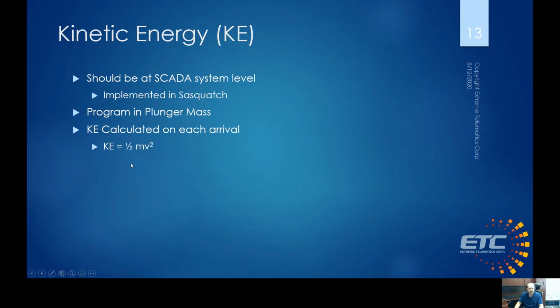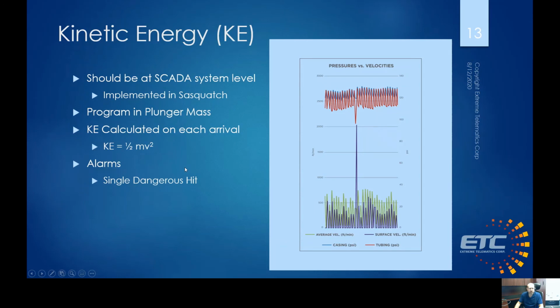And so we can calculate kinetic energy in imperial or metric. It's up to you. Those units can also be set in the sensor so that you get back the calculated value and the units that you want. And then once we have the kinetic energy, whether this is done in your SCADA system or whether it's done in the sensor itself, we can start to alarm in real time, because now we have every arrival's kinetic energy. Instead of just looking at the number of arrivals or the velocity of arrivals, we can get the kinetic energy each time so that we can identify single dangerous hits, consecutive hard hits, or we can add up cumulative long-term kinetic energy to try and predict the spring wear or the wear on the plunger.